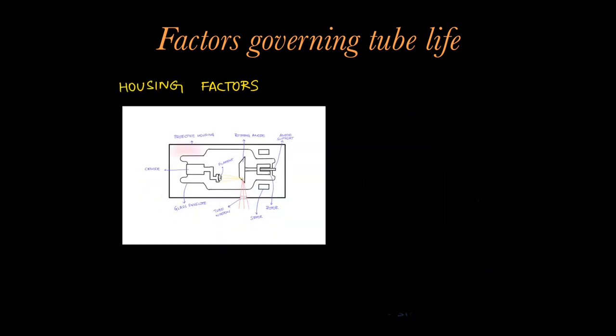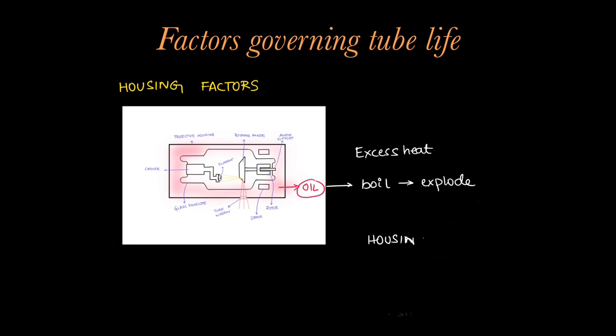The tube housing contains an oil bath, as discussed in part 1 of the video. This is designed to remove heat from the x-ray tube, but excess heat can cause the oil to boil and explode. Hence, separate housing cooling charts are available for each x-ray tube.